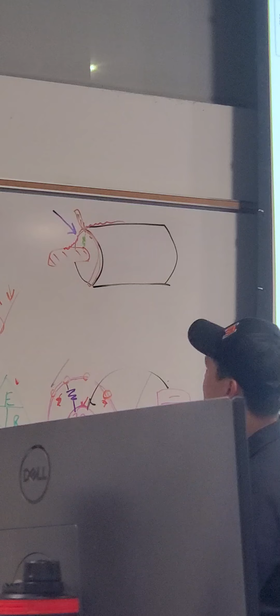So what can we do about that? This is when we apply our guard terminal. What it would actually do is come into this equation, and it would be subtracted from the internal calculations that happen on this guy. So then all you're really looking at, at the very end, would be what you meant to test all along, which would be the resistance internally of the cable insulation rather than any unintended outside paths.